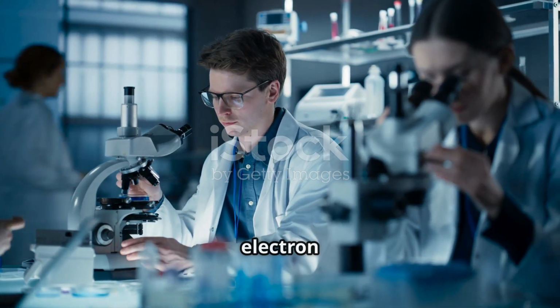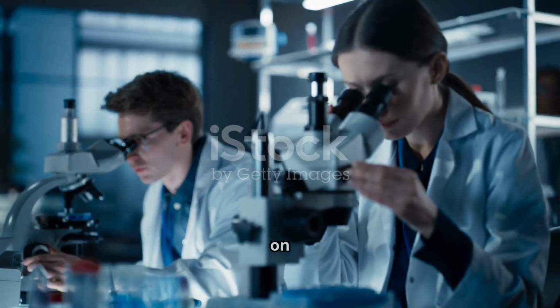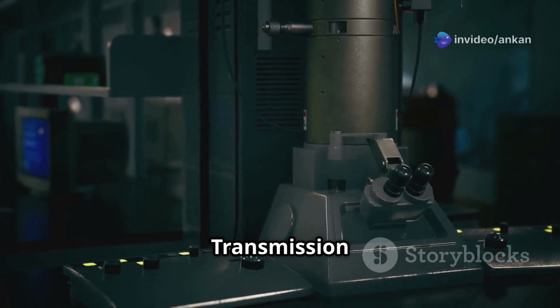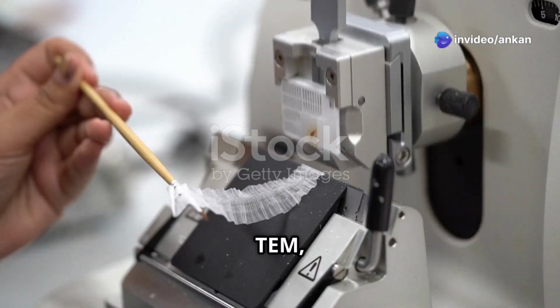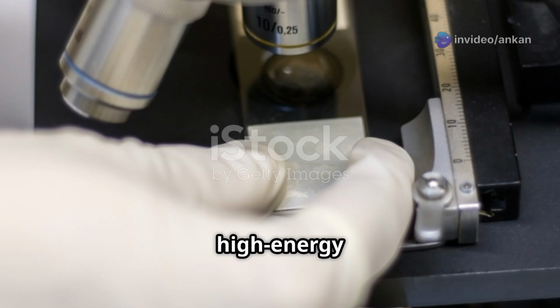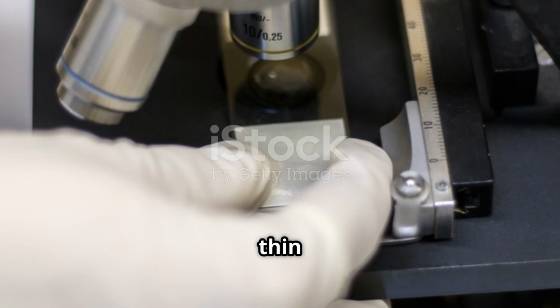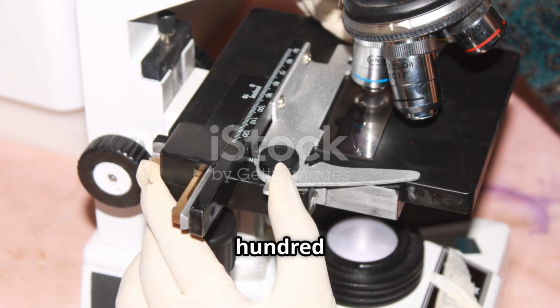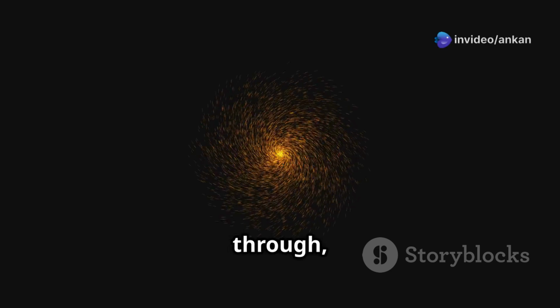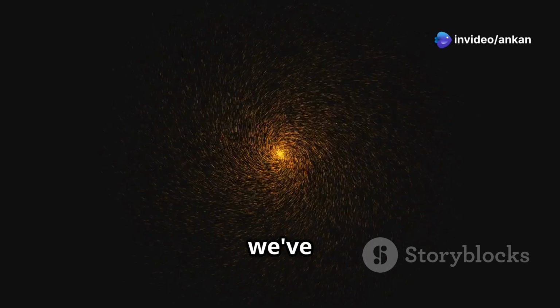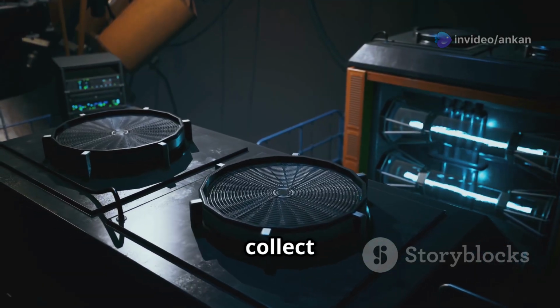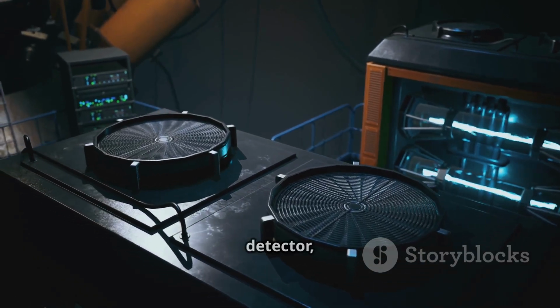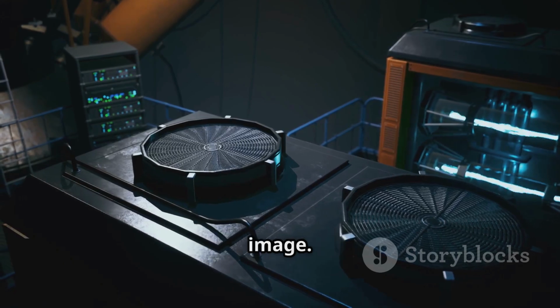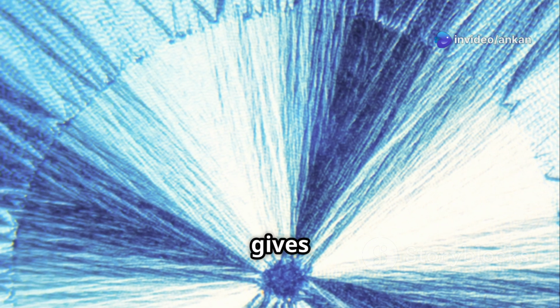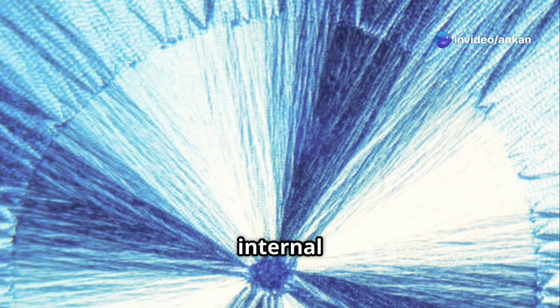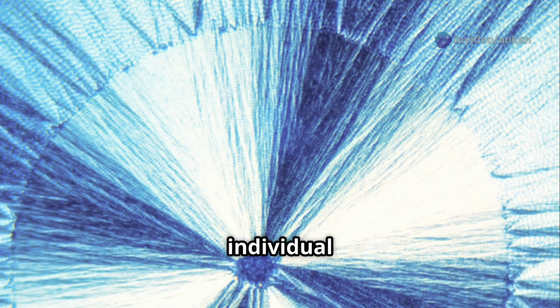There are two main types of electron microscopes, and each offers a different perspective on the atomic world. The first is the Transmission Electron Microscope, or TEM. In a TEM, a broad parallel beam of high-energy electrons is fired through an extremely thin slice of the sample, typically less than 100 nanometers thick. As the electrons pass through, they are scattered by the atoms in the specimen, as we've discussed. The electromagnetic lenses then collect these transmitted electrons and project them onto a detector, forming a two-dimensional black and white image. A TEM is like a slide projector. It gives you a high-resolution view through the object, revealing its internal structure, crystal lattice, and even individual atomic columns.